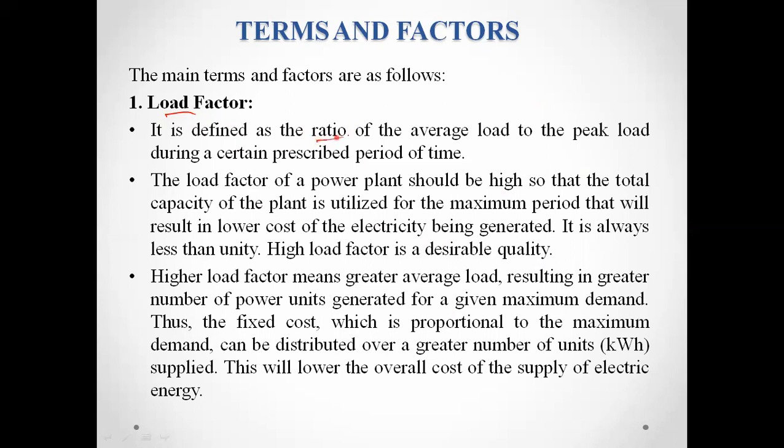It is the ratio of the average load to the peak load during a certain prescribed period of time. So the load factor of the plant should be high, so that the total capacity of the plant is utilized for the maximum period, and that will result in a lower cost of the electricity being generated. So the load factor should be high, so that there will be a reduction in the cost of electricity.